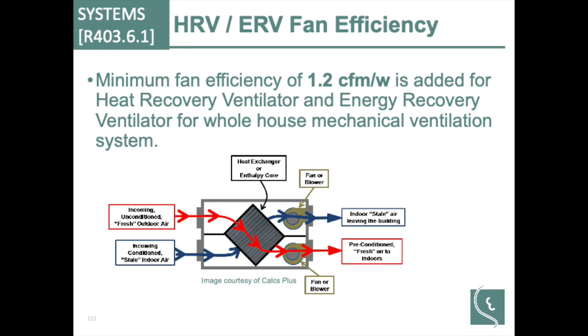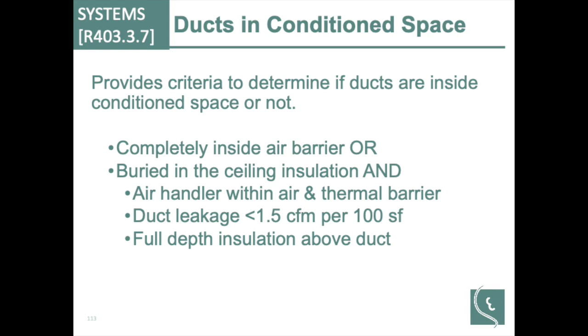Ducts in conditioned space. The code has provided some guidance as to how we know if the ductwork is in the conditioned space or not. And this part of that goes back to air leakage testing. But it notes that obviously if all your ducts are completely inside the air barrier, you are in the conditioned space by definition. Or, going back to the buried in ceiling insulation, if the air handler is inside the air and thermal barrier, and when you do your duct leakage testing it comes in at under 1.5, where regular duct testing is 3, and you have full depth insulation above the duct. So again, in this area, we're probably in R49, so you'd have to have a full R49 above the duct. If you meet all those criteria, then you are considered in the conditioned space.